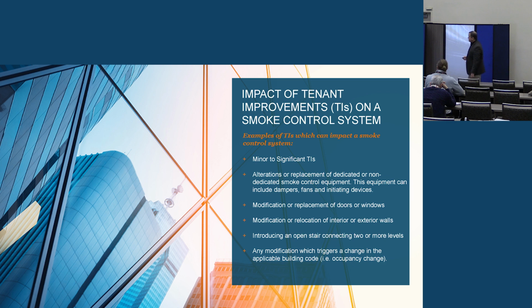So the relocation of interior walls, that's the big one. Tenant changes, and I'll show you an example of how a couple of walls can make a system completely unfunctional. Opening stairs, convenience openings. Say you have a large high-rise, and I'll give you a great example. My company, we just occupied a high-rise down in Columbia, and we took 3 floors of that high-rise. And somebody's like, oh, we should have convenience stairs so we can just go up and down in our space. As soon as I open up the floors, could that impact my sandwich pressurization if I have it? Could that impact all the smoke control in general? Absolutely.